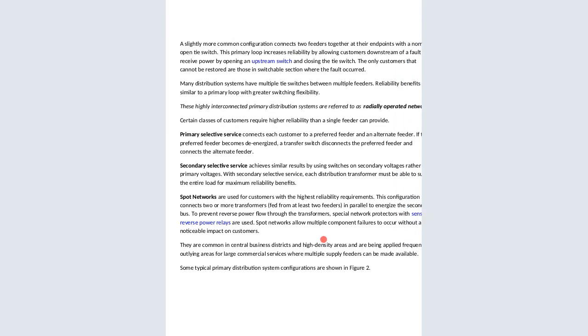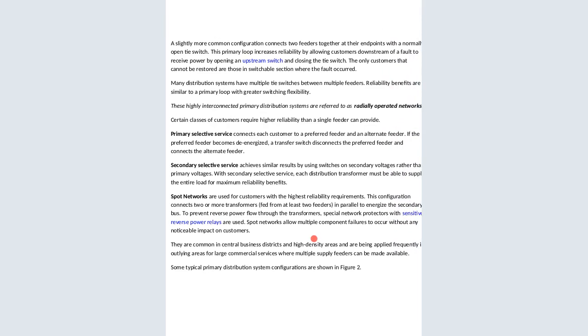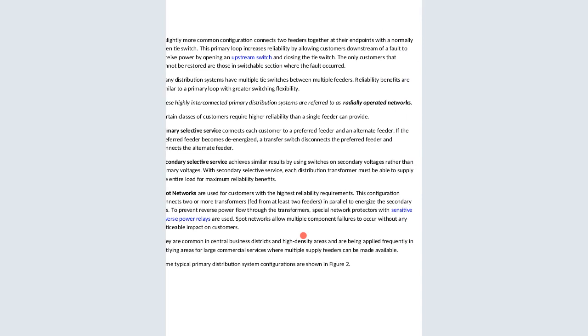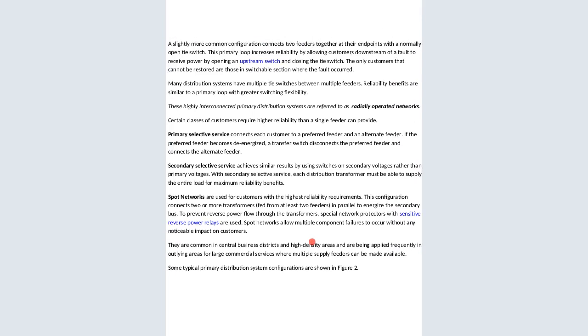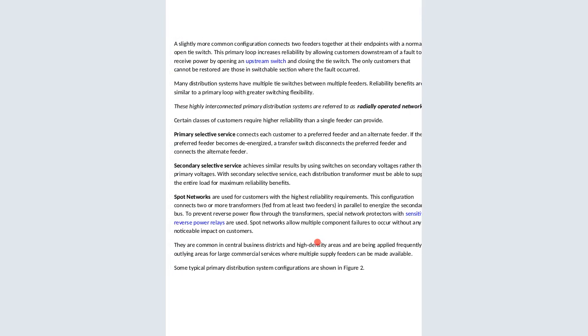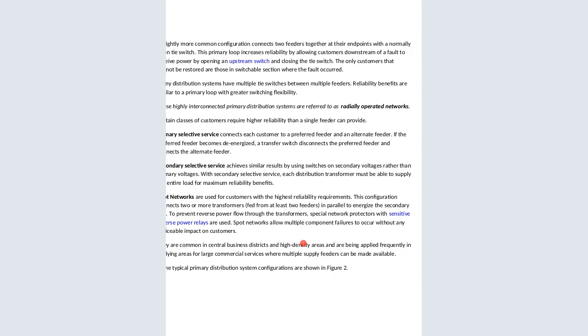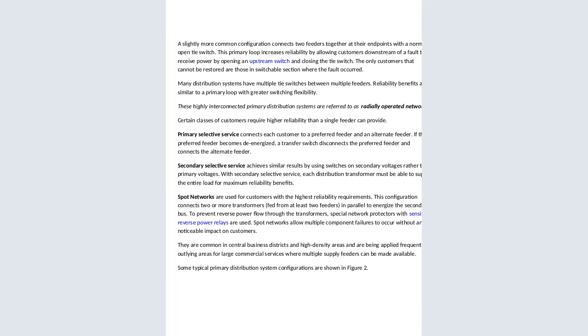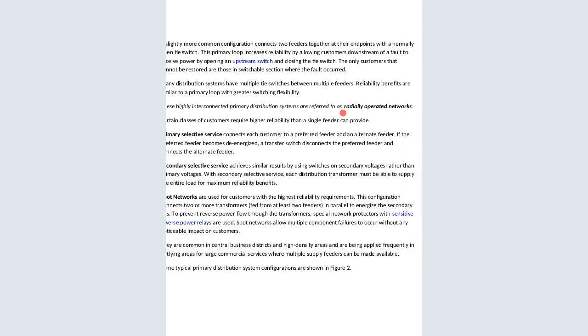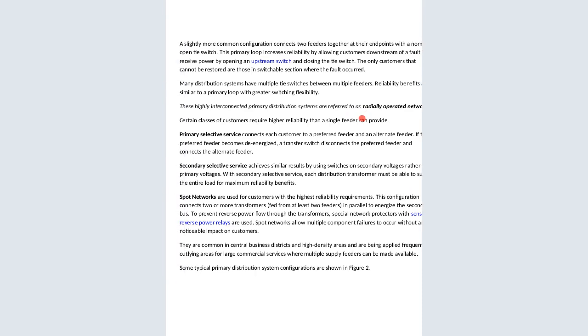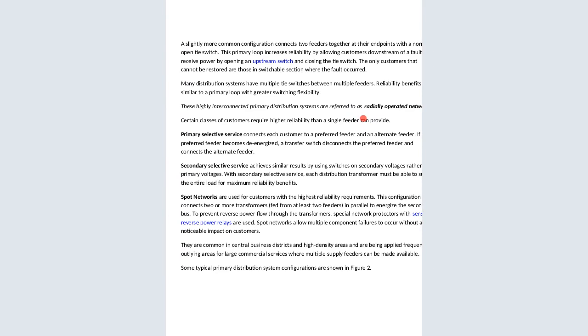A slightly more common configuration connects two feeders together at their endpoints with a normally open tie switch. This primary loop increases reliability by allowing customers downstream of a fault to receive power by opening the upstream switch and closing this tie switch. The only customers that cannot be restored are those in the switchable section where the fault occurred.